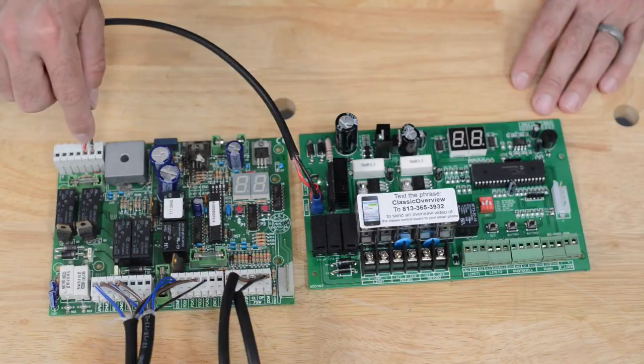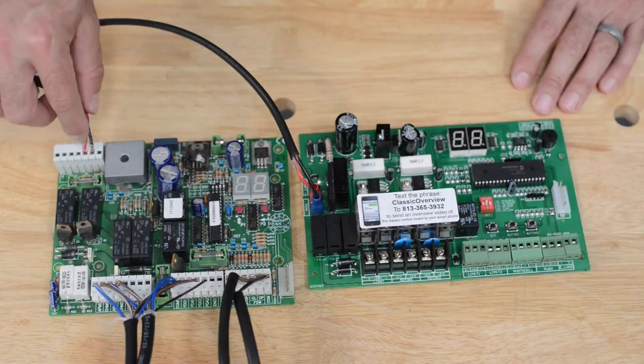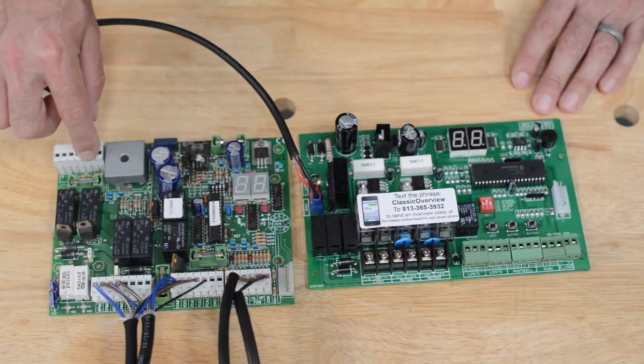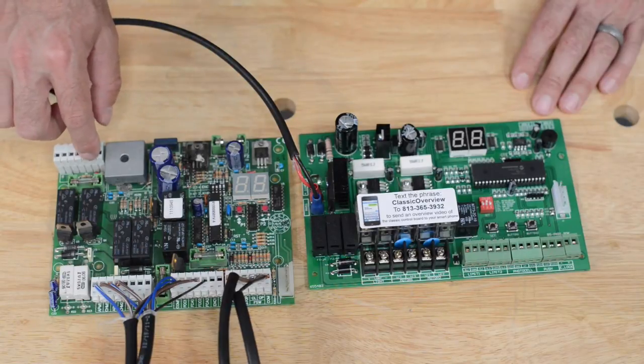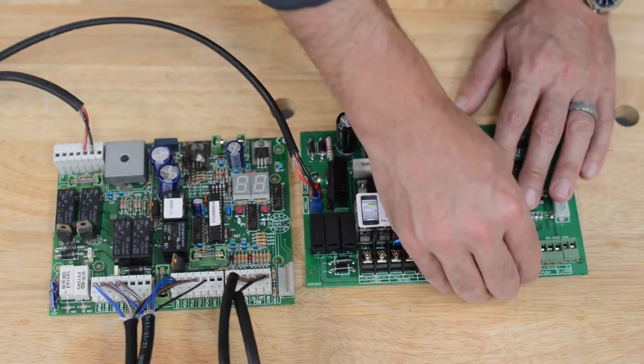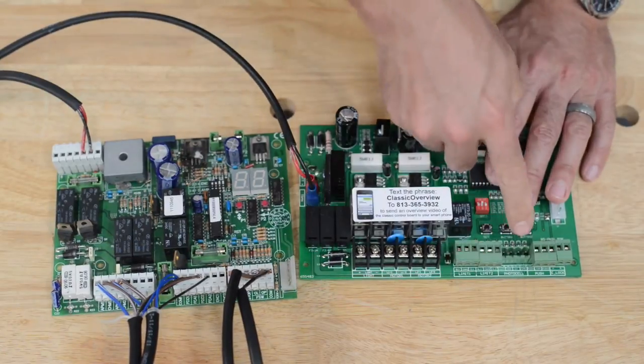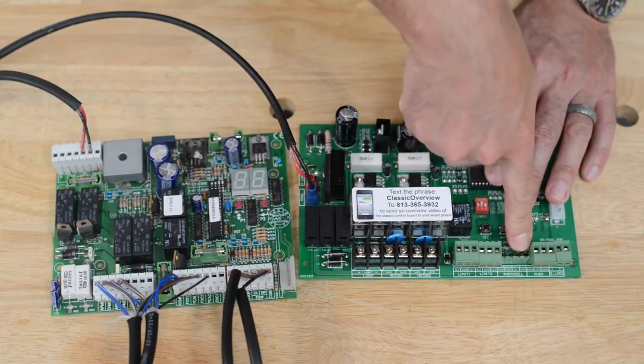Lastly, on the CN1 block, we have output power to our exit wand. This could be output power to any accessory, however, it's basically going to the 24V positive and negative. On this, it would be going to the photocell block, which you will see has a positive 24V and the ground.